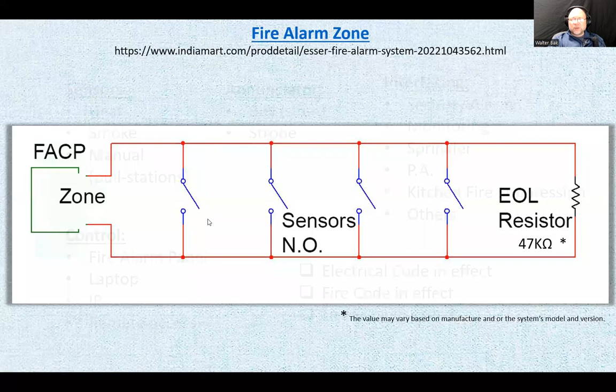Now, if one of those sensors closes, instead of seeing an open loop, which is infinite resistance, it is going to see a closed loop, which is zero resistance or close to zero, and then it is going to trigger into alarm condition. Okay? So that's how the zones work for the fire alarms. Sensors: basically heat, smoke, or manual, such as pull stations. Annunciators: bell, siren, or strobe. Interfacing: they can be interfaced with security alarm. So security alarm and the fire alarm can feed off each other, but it has to be done according to the rules and regulations that apply to the area that you're in. So always consult. The monitoring station is the best source to do that.